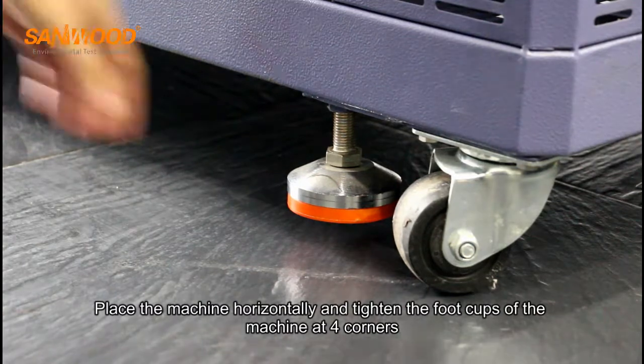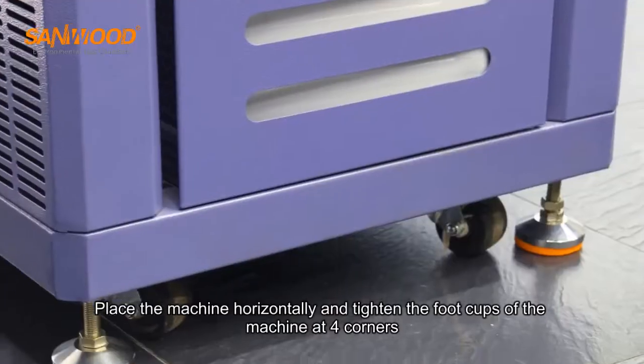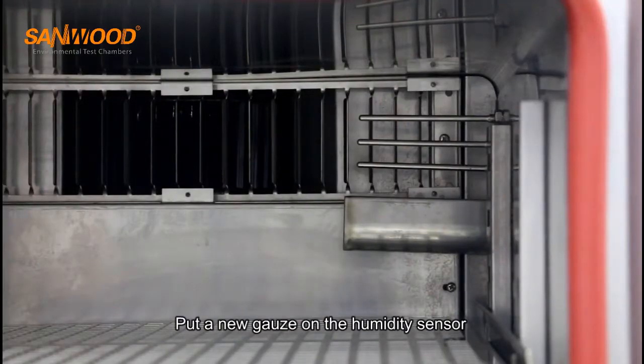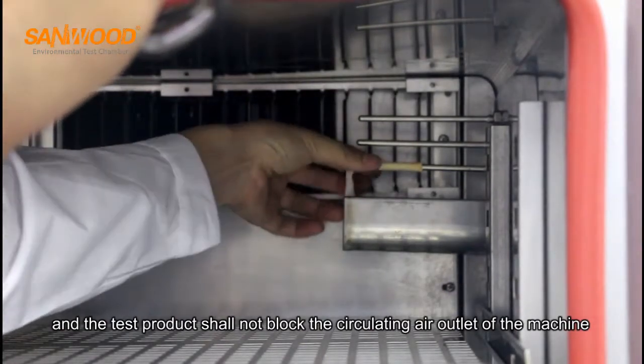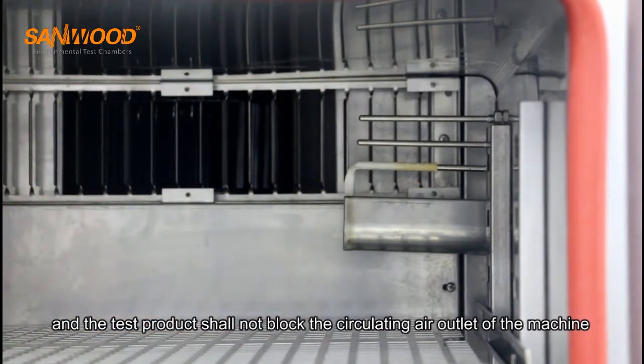Place the machine horizontally and tighten the foot cups of the machine at four corners. Put a new gauze on the humidity sensor, fix the sample holder on the rack of the machine, and the test product should not block the circulating air outlet of the machine.